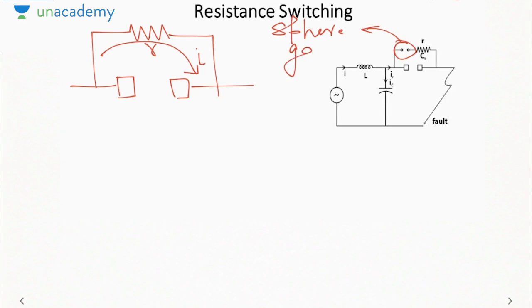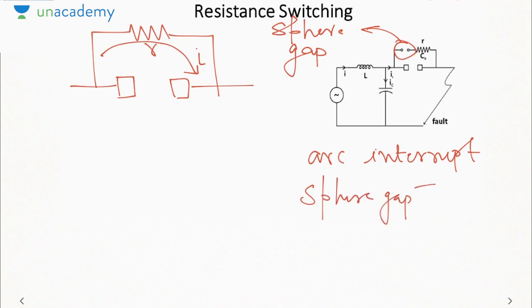Now whenever you interrupt the arc, a high frequency restriking voltage will be induced across the circuit breaker, due to which the air between the sphere gap will ionize, due to which an arc will be struck between the contacts of the sphere gap, due to which this resistance will be connected in the circuit. So whenever we interrupt the arc, the sphere gap becomes short circuited. Okay, so that means the resistance will be in the circuit.